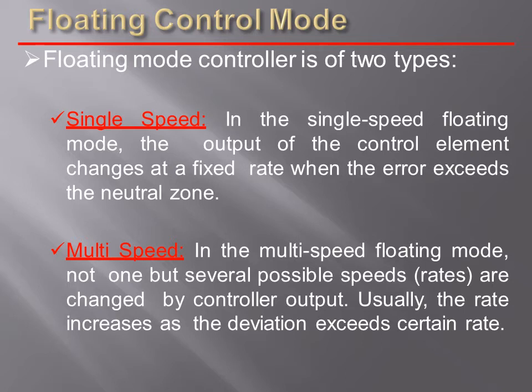In single speed floating mode, the output of the control element changes at a fixed rate when the error exceeds the neutral zone. In the multi-speed floating mode, not one but several possible speeds are changed by the controller output. Usually, the rate increases as the deviation exceeds a certain rate.